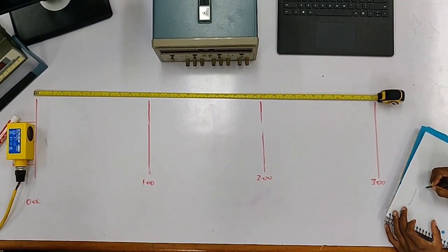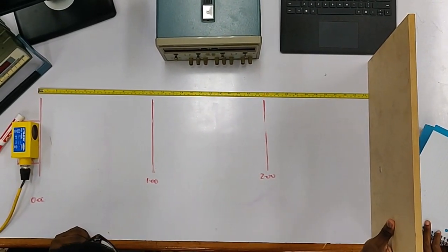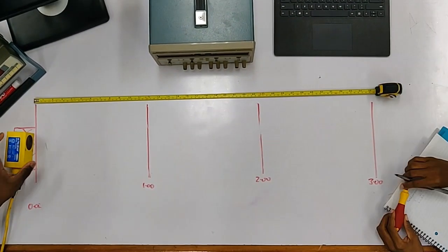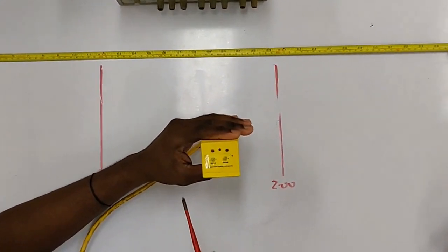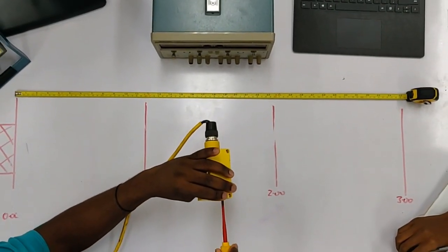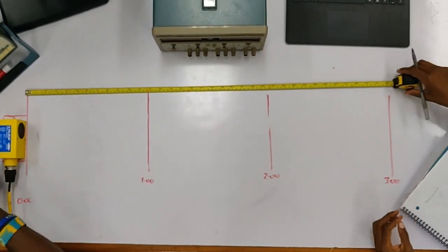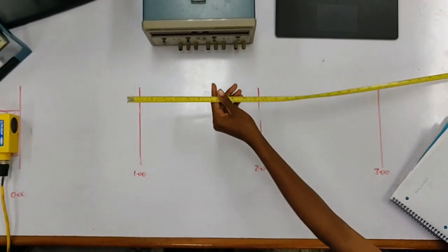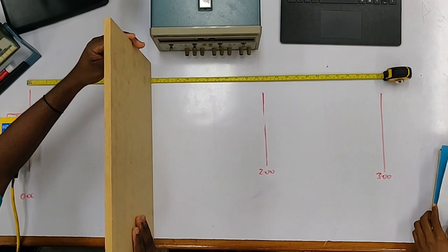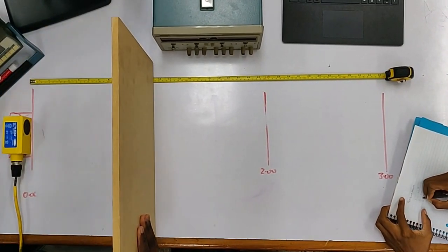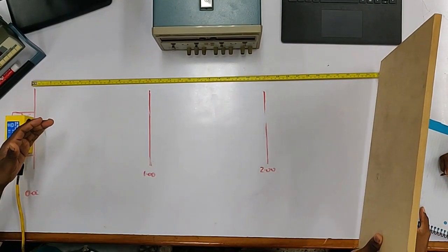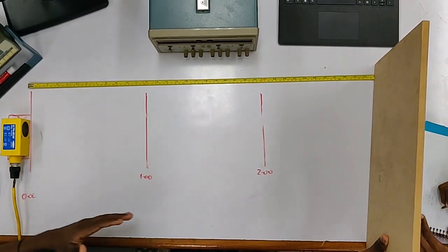You will notice that the uncalibrated sensor is outputting incorrect voltage values. At the end, we will formulate an equation which we can use to adjust the null and span. Alright, now we will adjust the null and span to the appropriate values which we calculated. Just make sure to recheck your references, and we will repeat the steps until the sensor is accurately and precisely calibrated. Now you can see that with the properly calibrated sensor, it is displaying the correct voltage output. Report each value in case further calibration and adjustments are needed.